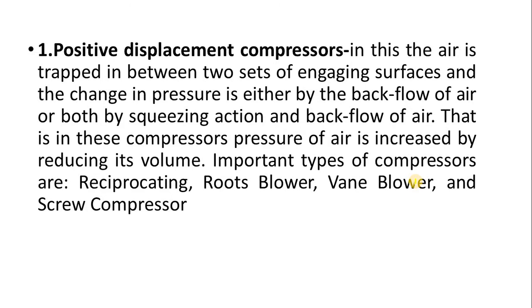Now, what is exactly the positive displacement compressor? In this particular kind of compressor, air is trapped between two sets of the engaging surfaces and the change in pressure is either by backflow of air or both by squeezing action and backflow of air. Compressors like reciprocating, Roots blower, vane type, and screw compressor come under positive displacement compressors.